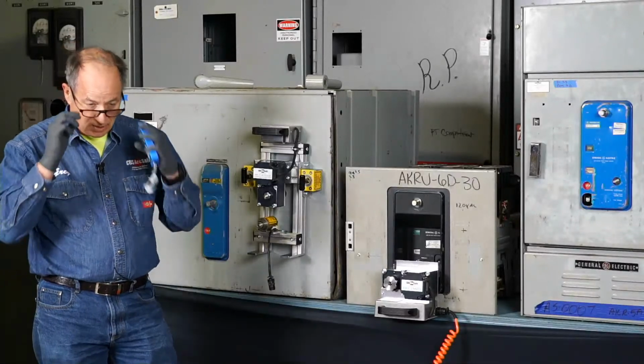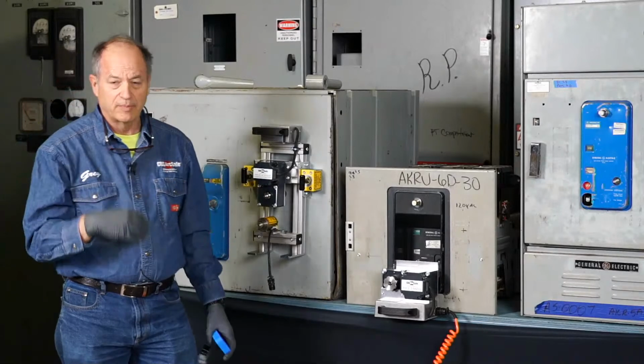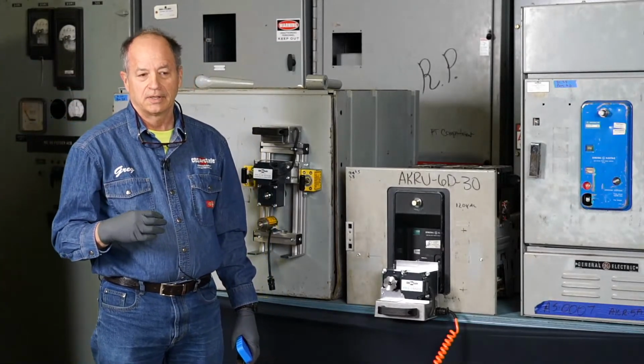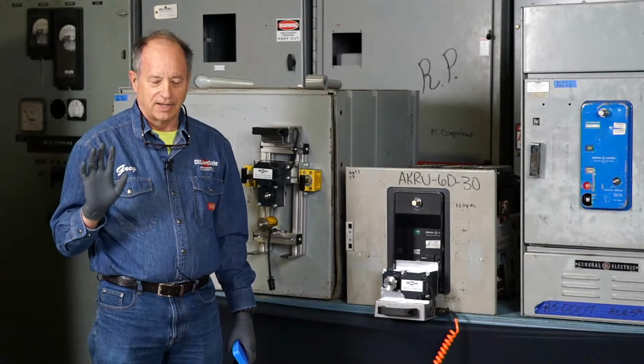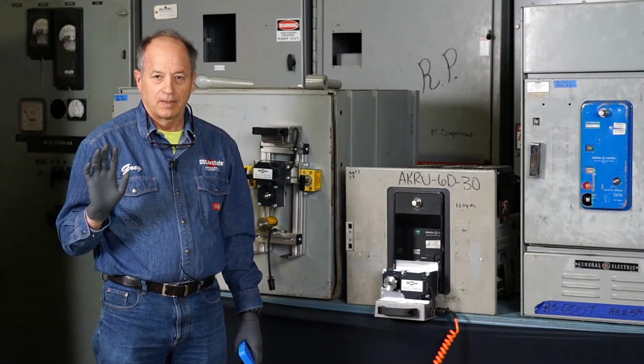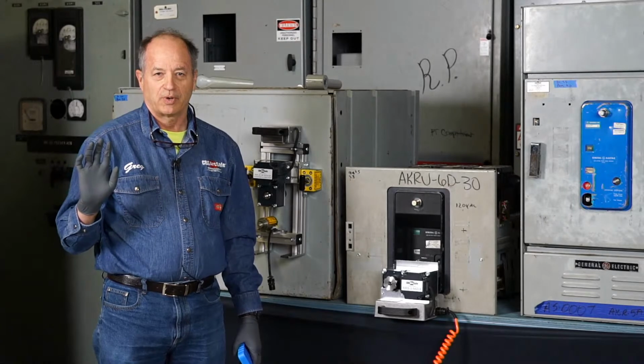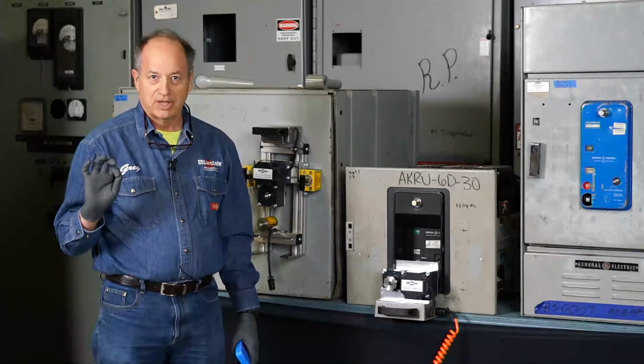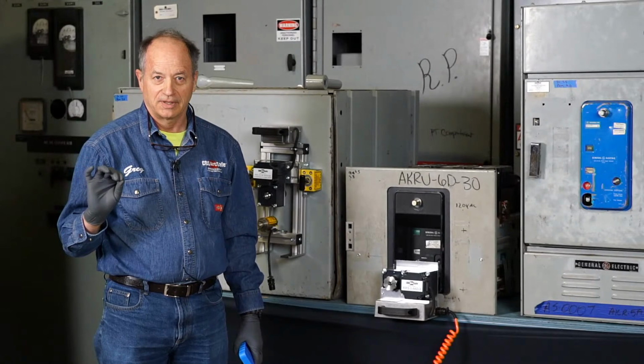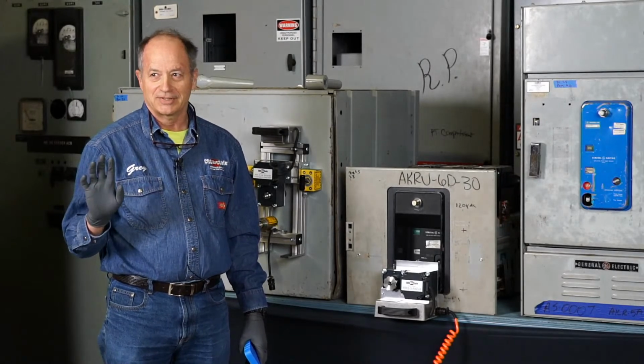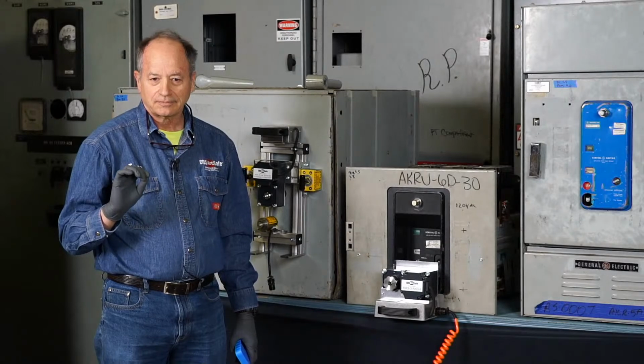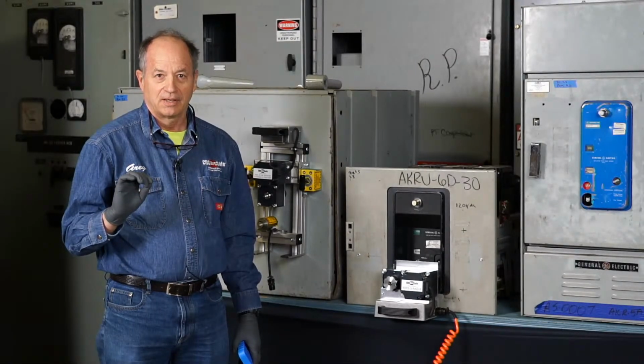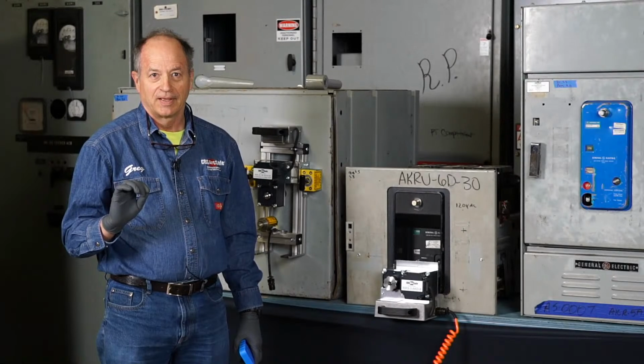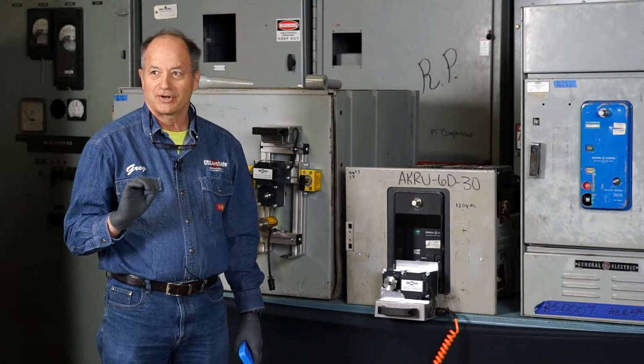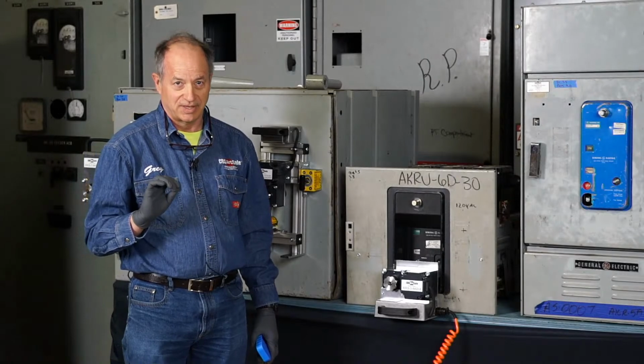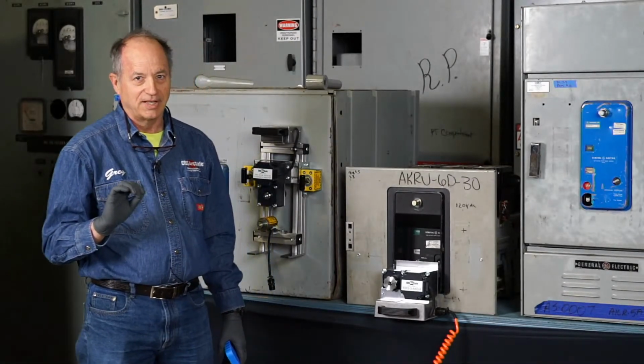One of the things to know is sometimes when you first start getting involved in remote racking, you may have somebody like - I couldn't make these names up if I tried. I went to a facility, won't say which one, but there were two guys, one named Jughead, the other Neanderthal. Both had that on their hard hats. They said if it took 10 foot-pounds to get it in, Neanderthal could use 80. A lot of things got broke until they started using remote racking and remote switching, because things were being put in a little bit harder than they needed to be.